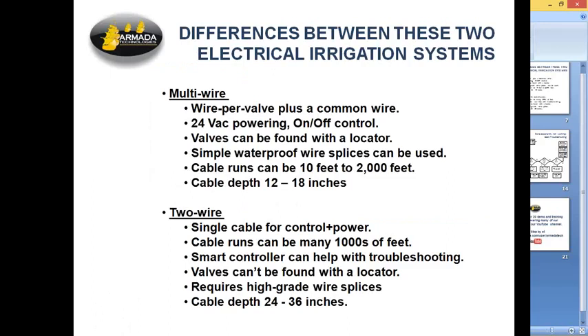One thing I should mention as a difference between the two systems is that 30-some volts on the control cable is there 24/7. It's there constantly. What that means is that the splices become more critical. The splices that are powered constantly get wet and there's moisture in the air, which encourages corrosion of the copper. So what you have to do is use a very high-grade DBY type splice when you're wiring between the control cable and the valves. That's a main difference, because one of the biggest failure modes in a two-wire system is exposed copper or damage to the splices in the valve box.